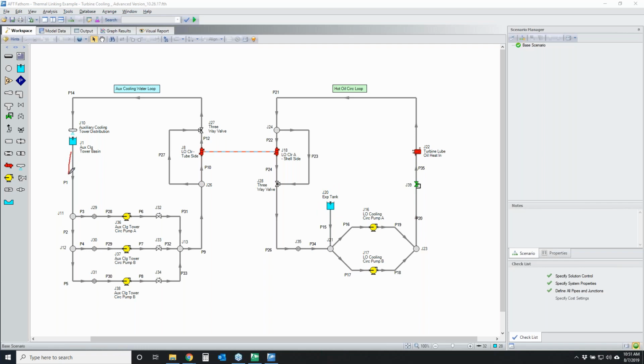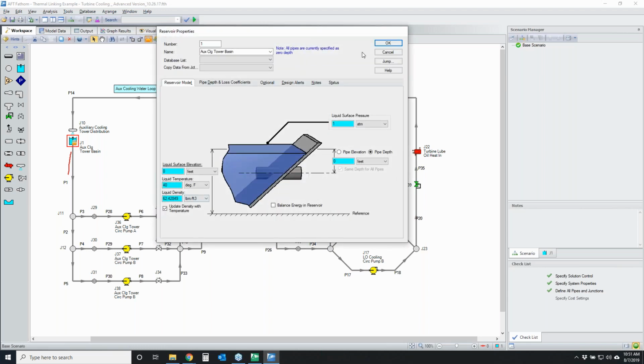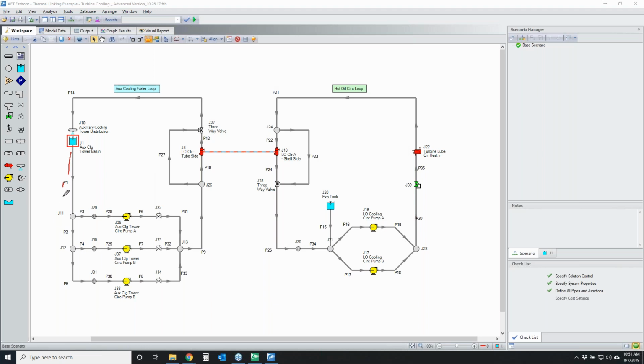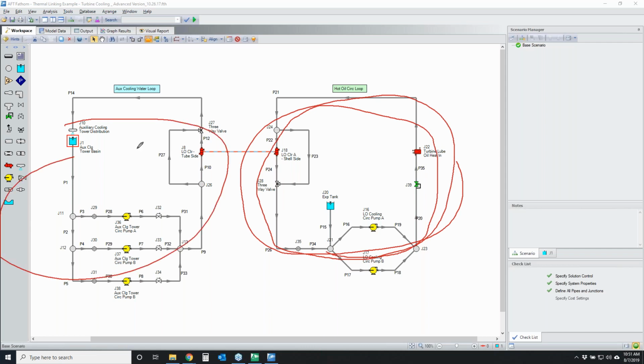So here's what we have going on. We have cooling water coming in, and that temperature coming in is going to be, what is it? 40 degrees Fahrenheit. So we have 40 degree Fahrenheit water coming in, and it's circulating throughout the system. And then we have this bypass, and we have a three-way valve here. This is where you can get even more fancy and sophisticated by using GSC again to really control your temperature. Let's say that your spray nozzles were sensitive to temperature, and you want to make sure that downstream, maybe you need a temperature of like 60 degrees or something. This bypass can help you control that a little bit more efficiently than just guessing and checking. Then on my right-hand side, I have hot oil that is circulating around the loop, and this is heating up the cooling water circuit fluid.